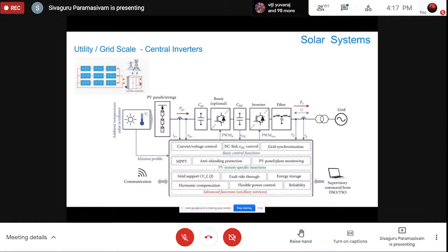That's what I'm trying to show here. Let's start from the left hand side. You can see the solar panels are getting connected to this system, where the DC positive and negative is connected to this inverter panel, and the inverter panel will immediately have some protection devices like surge protection, over voltage protection, and over current protection. So when there is a problem in the modules, the short circuit current should not affect the power electronics or the IGBTs in the system. So we have all the protections there. And then it's coming to the IGBT switch. Usually it will be a 6 pulse, 12 pulse, or 18 pulse configuration, depending upon the type of inverter that we use.